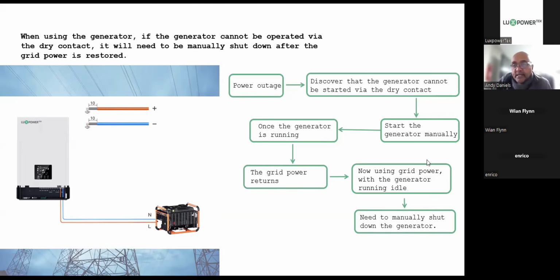Okay, so typically here's a flow diagram of what we would look at. If there's a power outage, your inverter will go to off-grid mode. If you discover that, like for instance now we've got terrible weather and we've had bad weather for days, there's no PV harvesting, and you notice if you're running an off-grid situation that your battery capacity is running down, you have to manually start the generator. Some of the questions that we've seen is, my generator is running, but there's no power going through to the loads and charging.